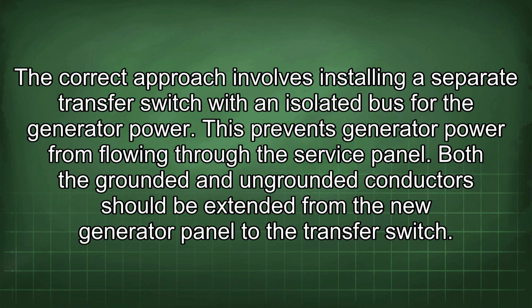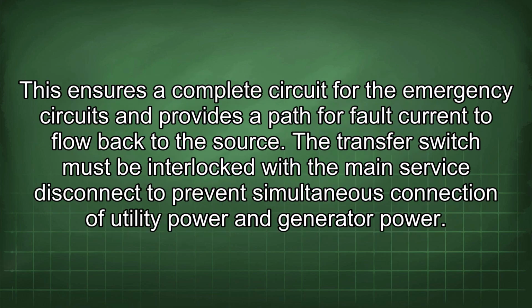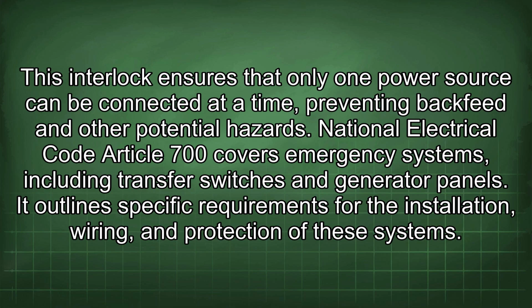The correct approach involves installing a separate transfer switch with an isolated bus for the generator power. This prevents generator power from flowing through the service panel. Both the grounded and ungrounded conductors should be extended from the new generator panel to the transfer switch. This ensures a complete circuit for the emergency circuits and provides a path for fault current to flow back to the source. The transfer switch must be interlocked with the main service disconnect to prevent simultaneous connection of utility power and generator power. This interlock ensures that only one power source can be connected at a time, preventing backfeed and other potential hazards.